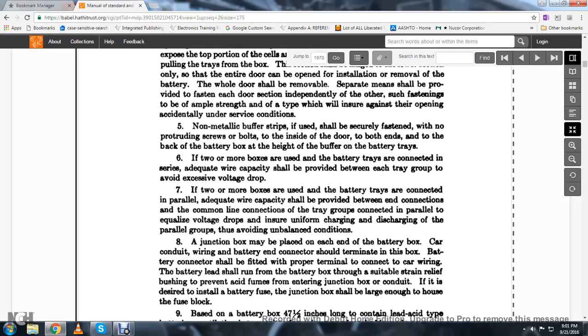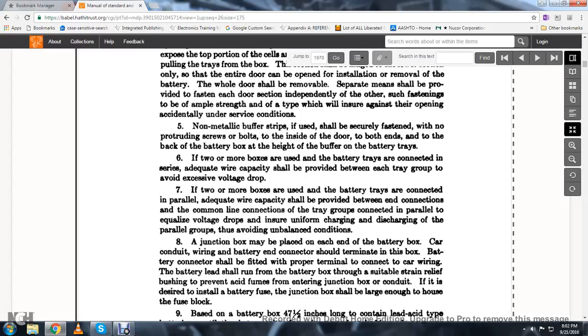Non-metallic buffer strips, if used, shall be fastened with no protruding screws or bolts inside the door, to both ends and the back of the battery box, at the height of the buffer of the battery trays. If two or more boxes are used with the battery trays connected in series, adequate cable capacity shall be provided between each tray group to avoid excessive voltage drop.